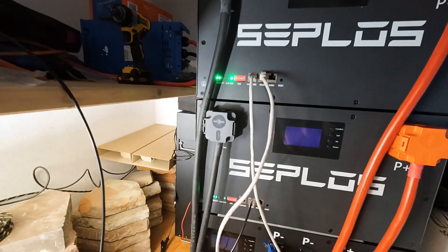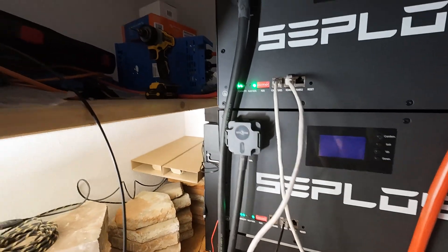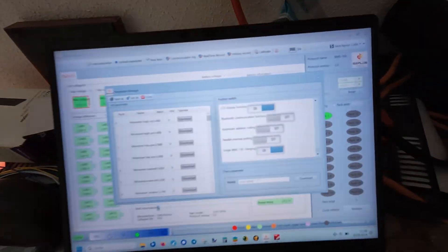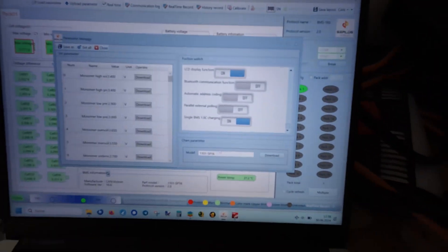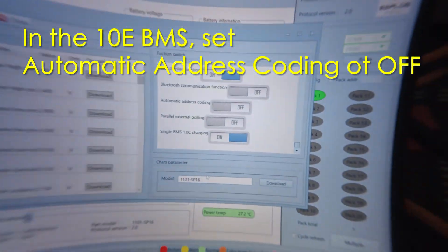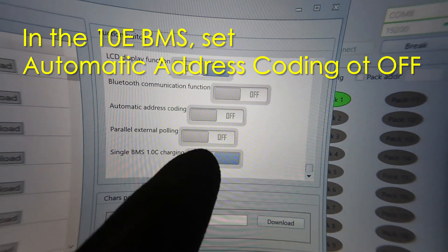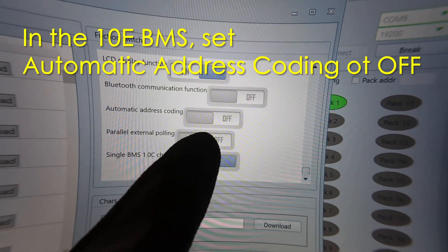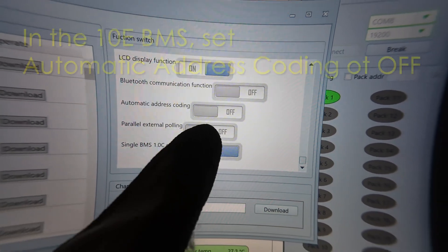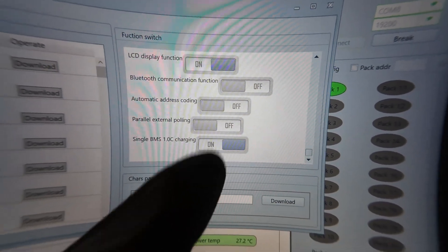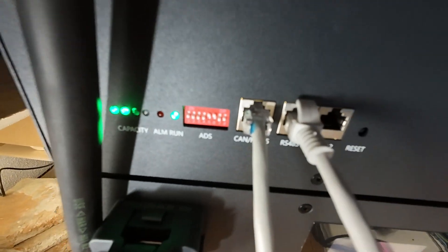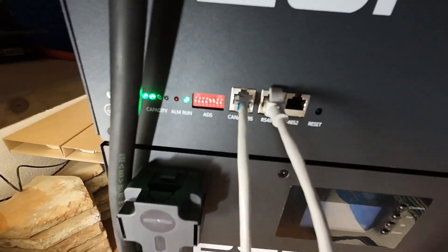Then you have to set one parameter here that is very important: automatic address coding. You have to set that to off so that it takes the coding here in the front. Only if you do that, then it will work.